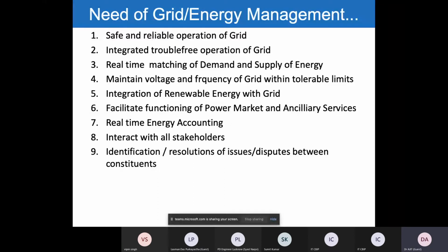Basically, when you increase the steam input to a generator, you are increasing the active power. That means you are stabilizing the frequency. And if there is a demand for reactive power in the system, if you have a load which has a low power factor and demands more reactive power, then it will reduce the voltage. That voltage has to be built up by feeding more excitation. You have to increase the excitation by using the AVR, automatic voltage regulator. That is a system used in the power station to match the demand and supply.